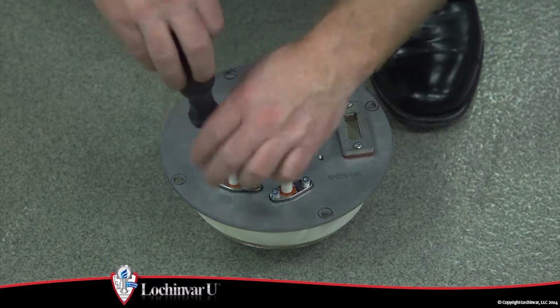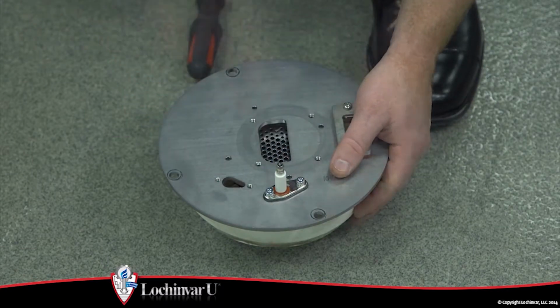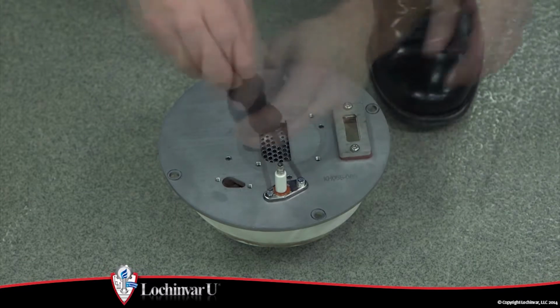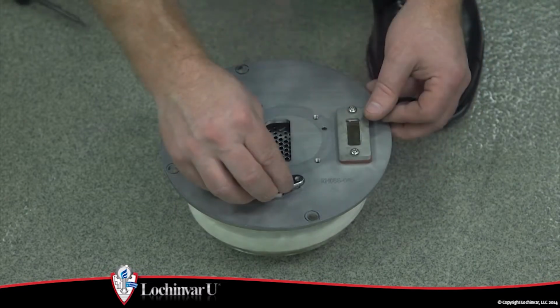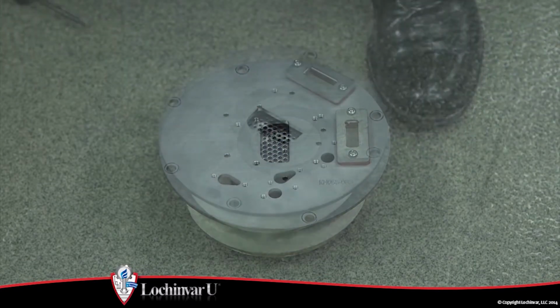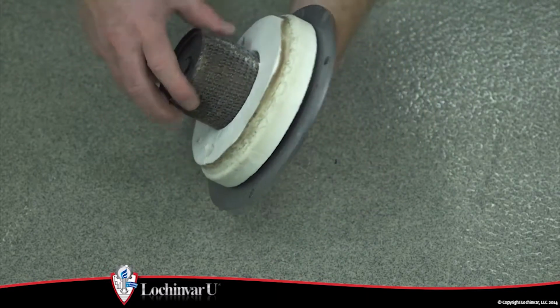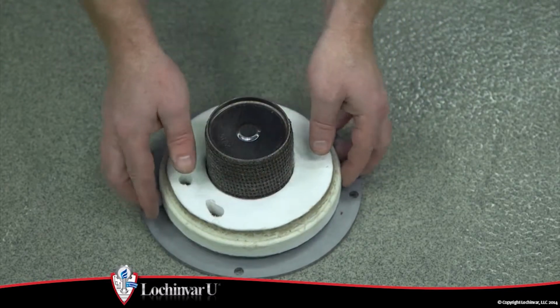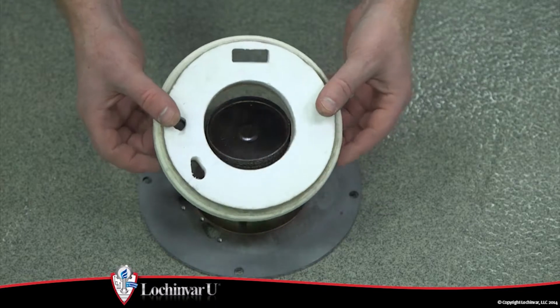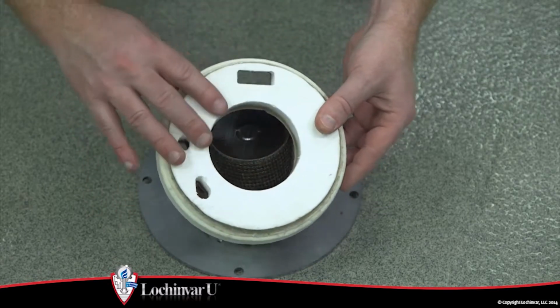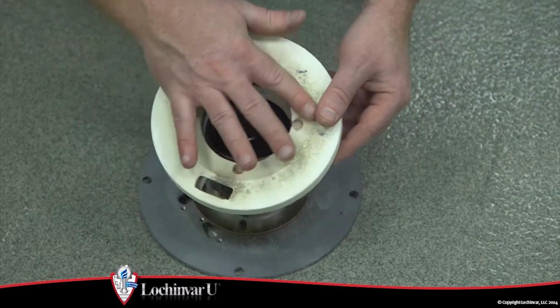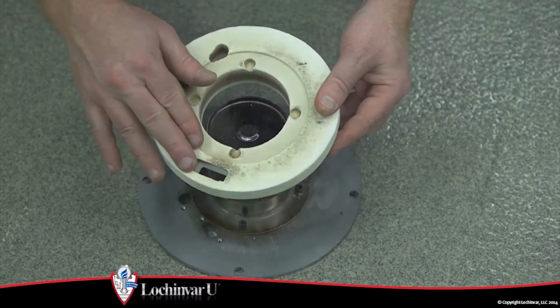Using a Torx wrench, remove the screw securing the igniter and flame rod to the heat exchanger door, and then remove. Now remove the insulating refractory from the heat exchanger door. Be sure to inspect the insulating refractory for damage. If the refractory is damaged, it must be replaced.